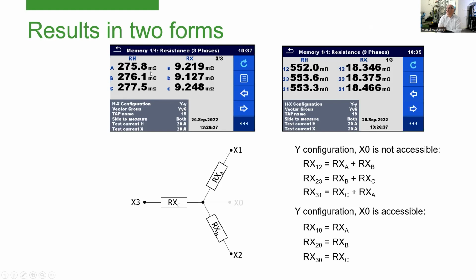Sometimes these values will be the same. It depends, for example, in this case, on whether the neutral X0 is accessible or not. If it's not accessible, then the values will be different. If it's accessible, then the instrument always measures between terminals X0 and X1, and this is the same as the winding resistance. Two methods of representing the results.